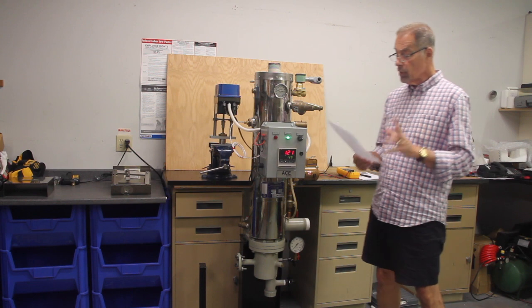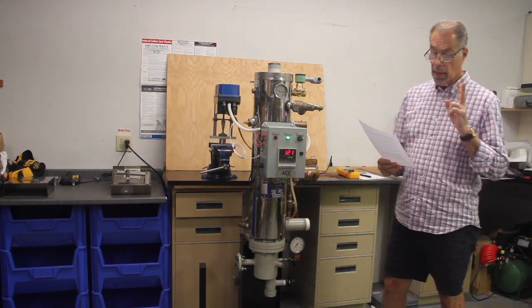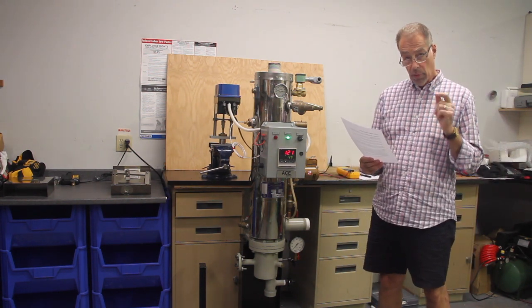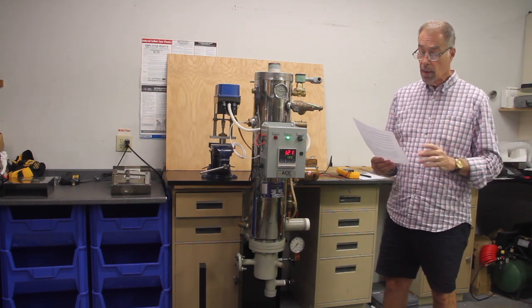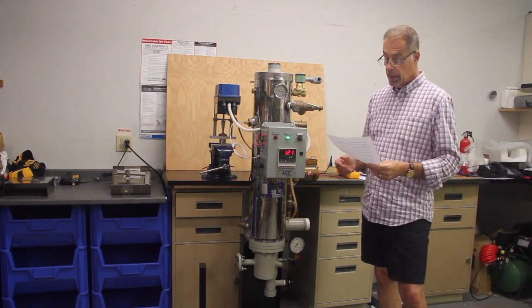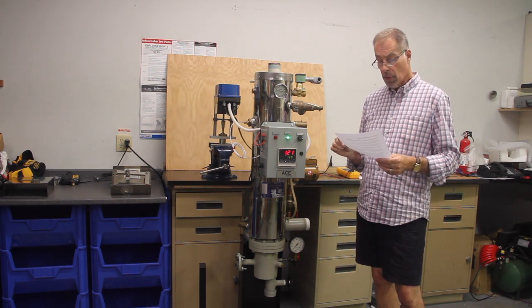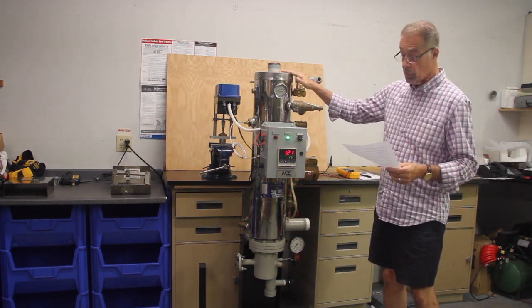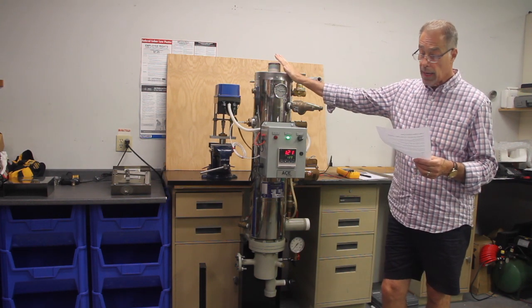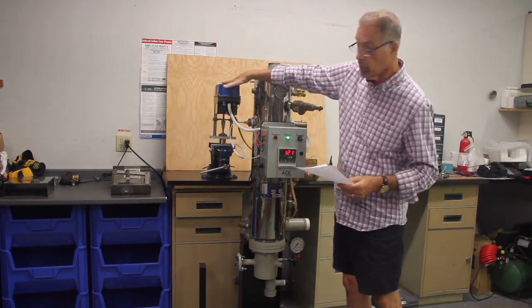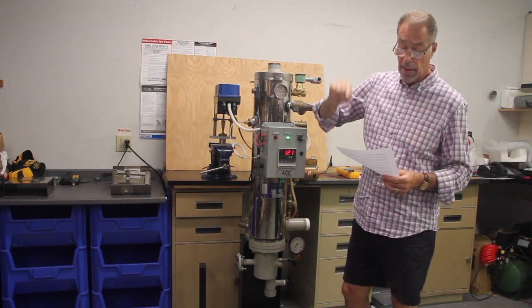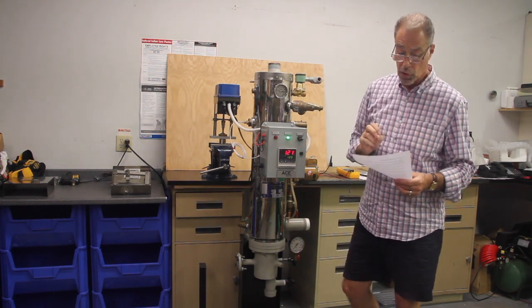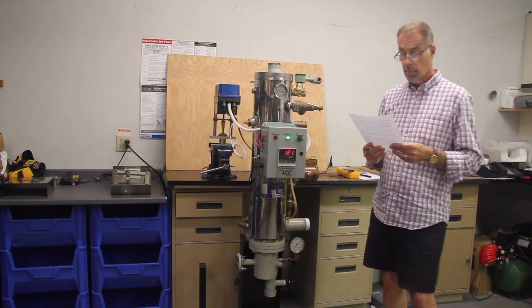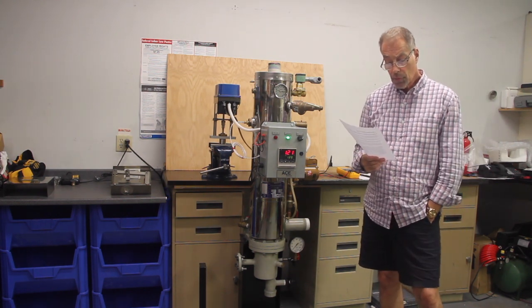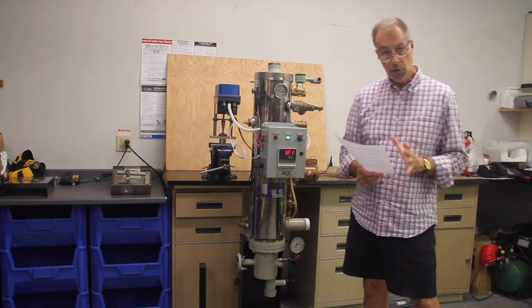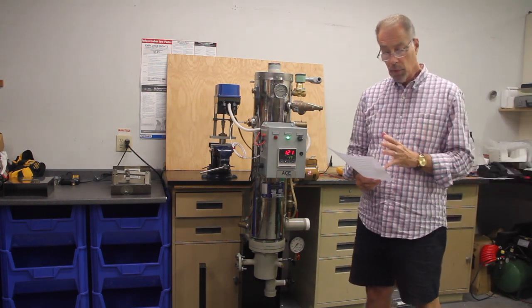So there's 3 heaters. 2 are domestic that I said are SIV8s. There's 1 Zamboni fill unit in another location that's an SIV6. And the only difference between the domestics and the Zambonis is the Zamboni is actually this size heater. This is a 6, okay? And the valve on the Zamboni is a 2-inch valve versus the valves on the domestics, which are 2.5-inch.